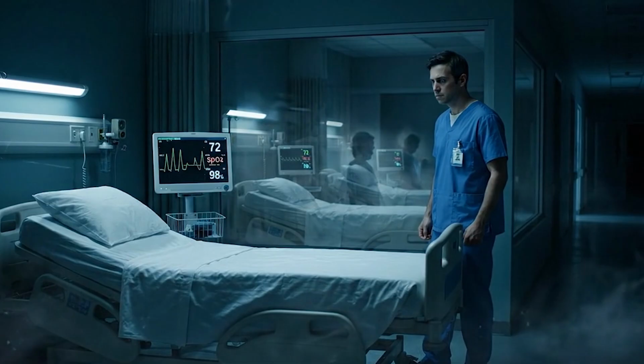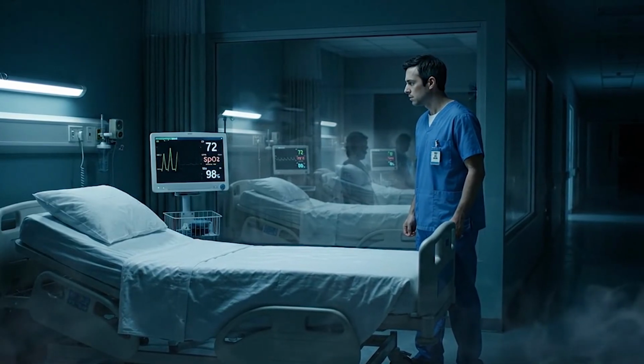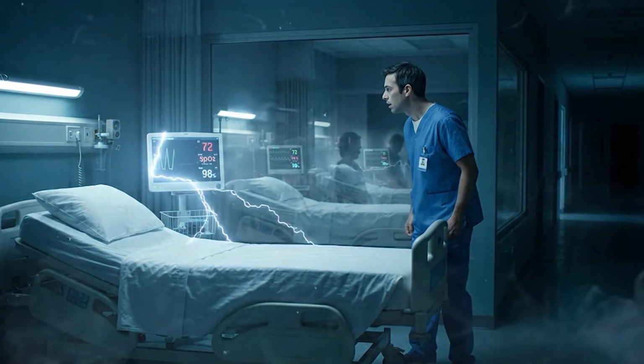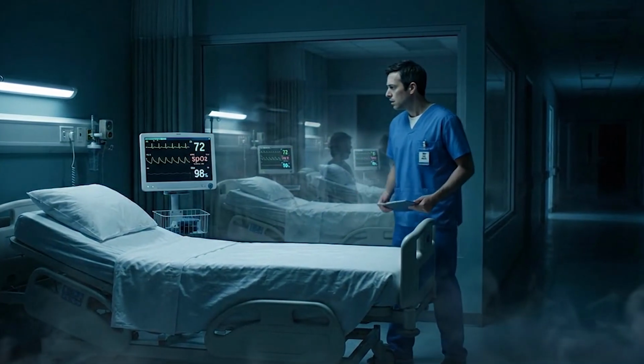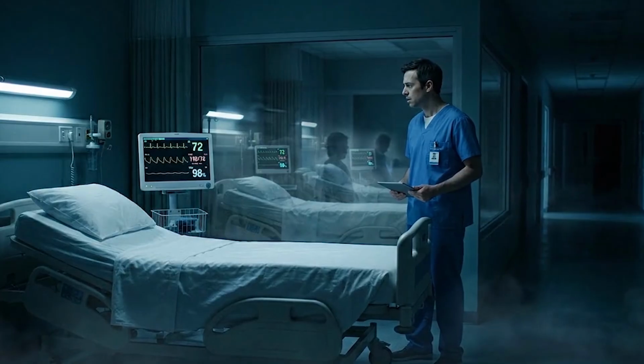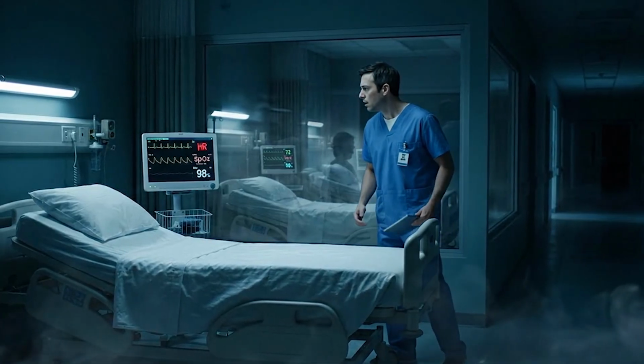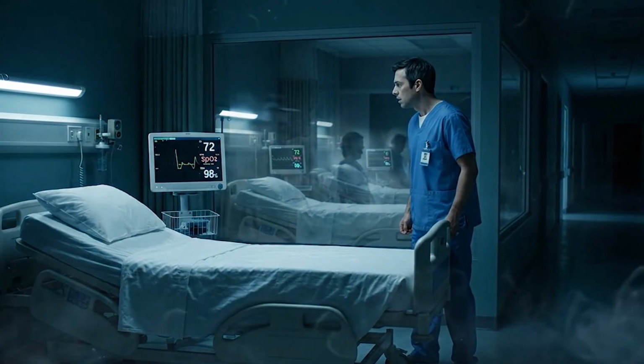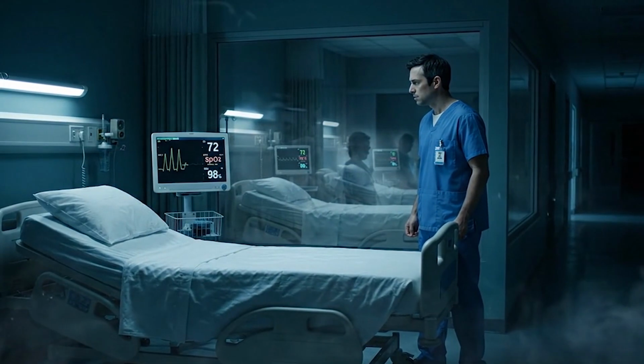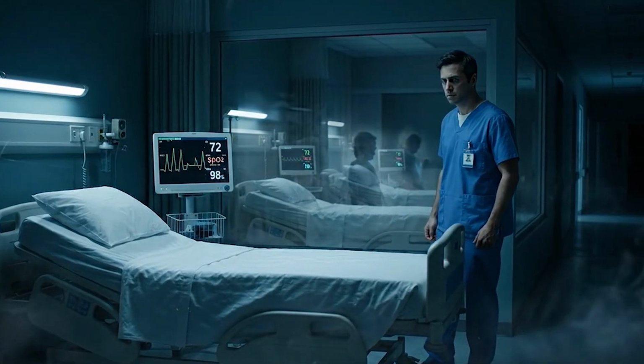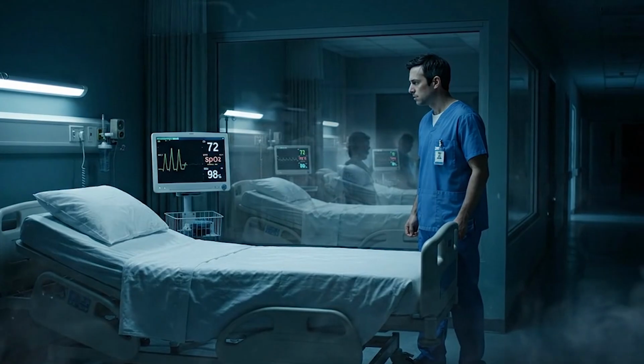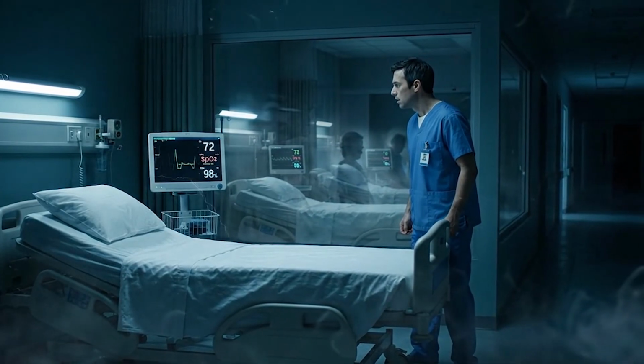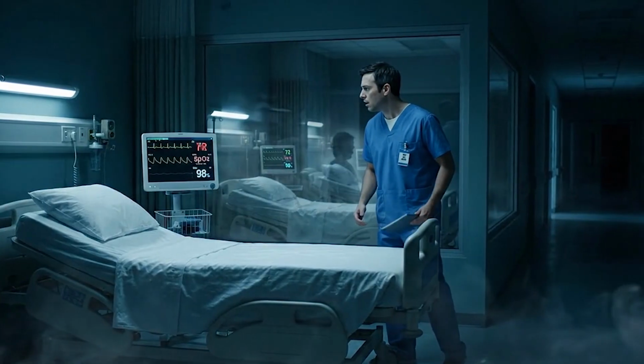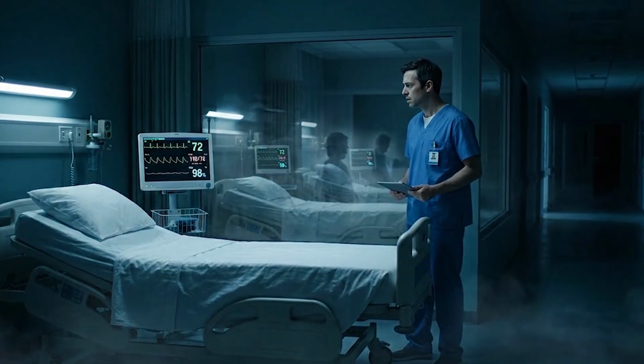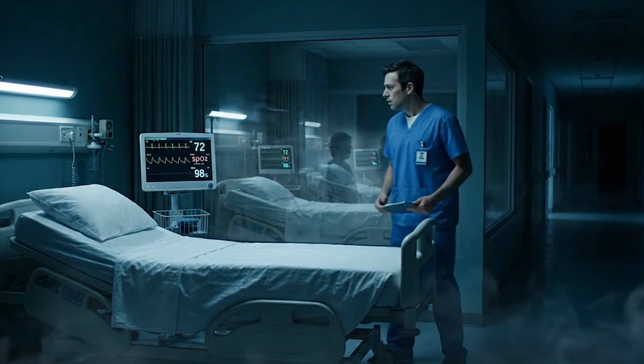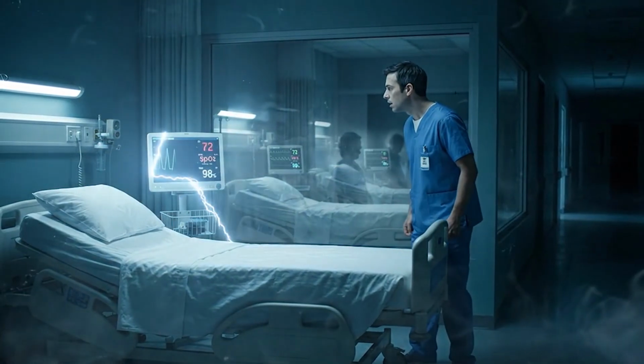What changed things was the temperature alarm. At 3:15 a.m., the phantom on bed 11 triggered a temperature alert. The monitor displayed a body temperature of 96.2 degrees Fahrenheit, which is below the normal range and triggers a hypothermia flag. The thing is, the temperature channel on a patient monitor requires a connected probe, a thermistor that sits under the tongue or in the axilla or in the esophagus, making physical contact with the patient's tissue. The temperature probe on bed 11 was lying on the mattress, connected to the monitor, but not to a patient, and the monitor was reading 96.2 degrees Fahrenheit from a probe touching a mattress surface.